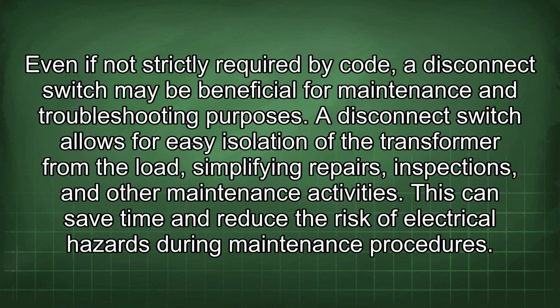Even if not strictly required by code, a disconnect switch may be beneficial for maintenance and troubleshooting purposes. A disconnect switch allows for easy isolation of the transformer from the load, simplifying repairs, inspections, and other maintenance activities. This can save time and reduce the risk of electrical hazards during maintenance procedures.